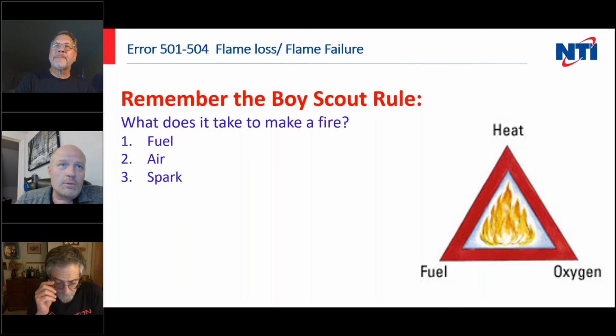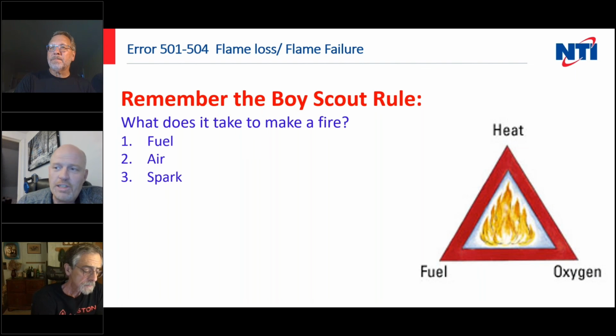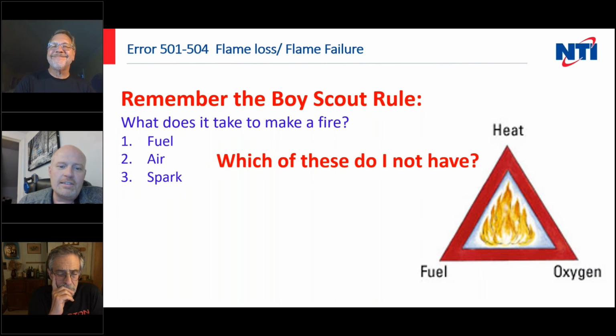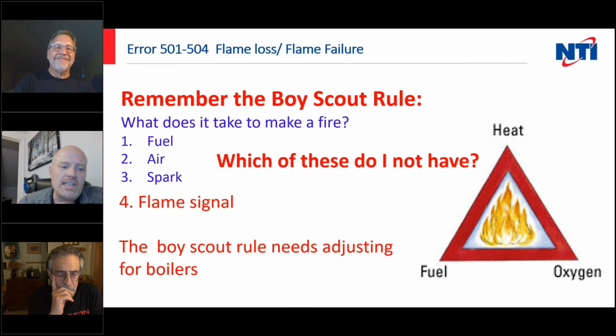So remember the Boy Scout rule. You need heat, fuel, and oxygen, or fuel, air, spark to have a flame. But the difference between the Boy Scouts and the boiler, and this is one thing I teach, this really should be, for the boiler world, a fire square, because the one thing it leaves out is flame signal.